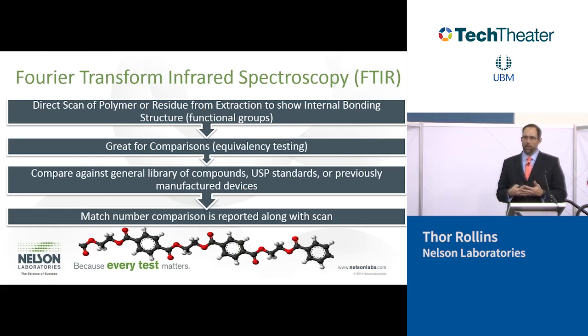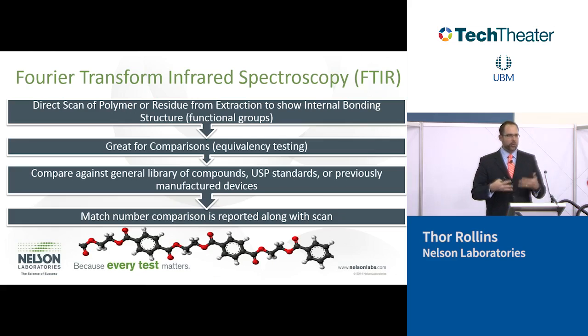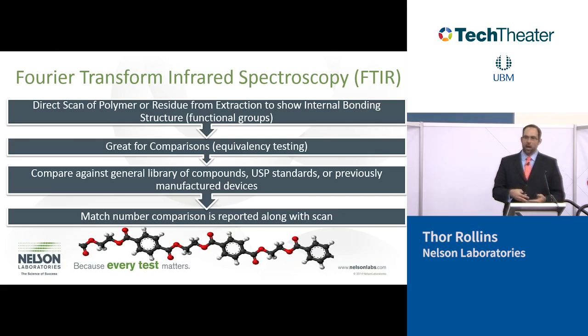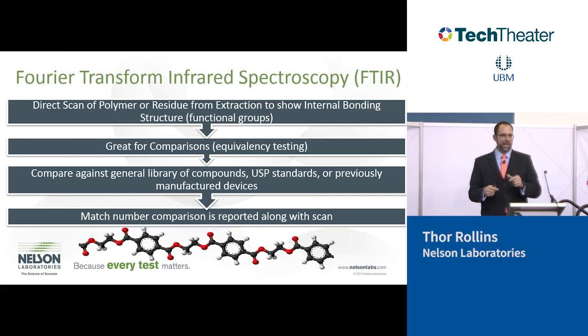What we can do, though, what's the power of the FTIR, is we can compare polymers to one another. And we can actually compare it to a USP grade polymer too. So let's say you're adding a polypropylene or changing to a polypropylene. We can take your polypropylene, scan it, and then take a USP grade polypropylene, scan it, and give you a comparison, a percent comparison. That's money when you're going to the FDA. You can say, look, we're as good as a USP grade polypropylene or whatever.